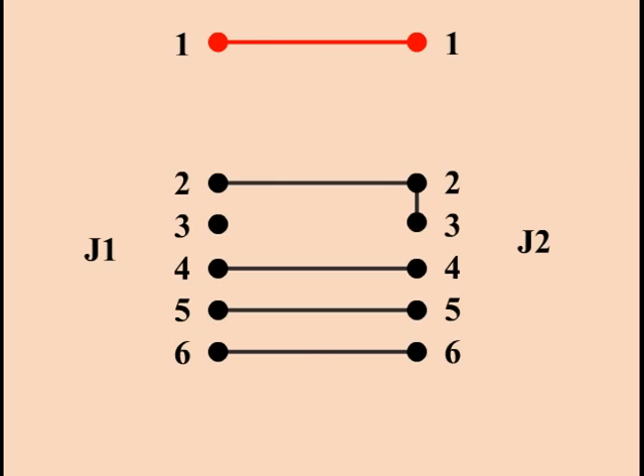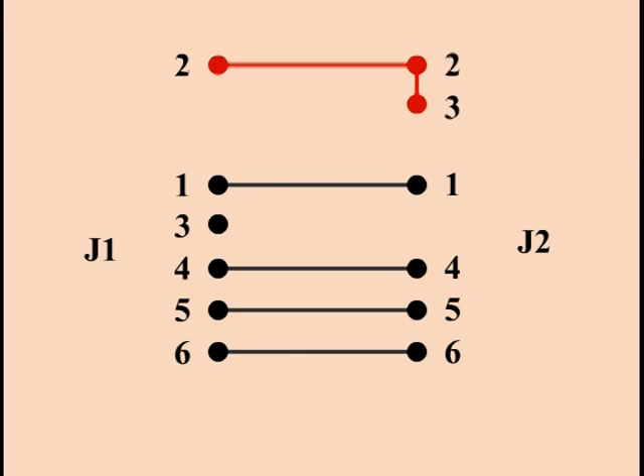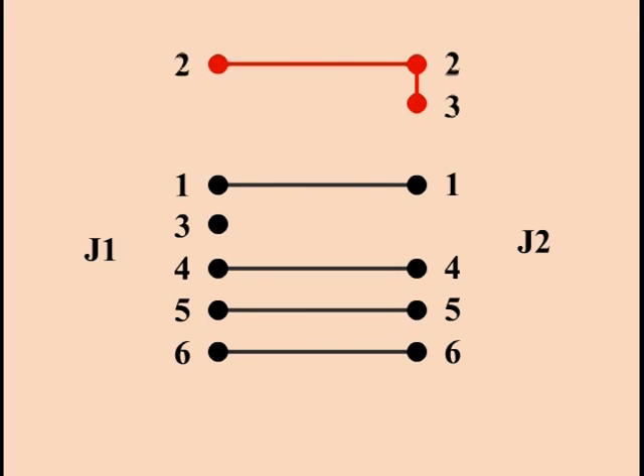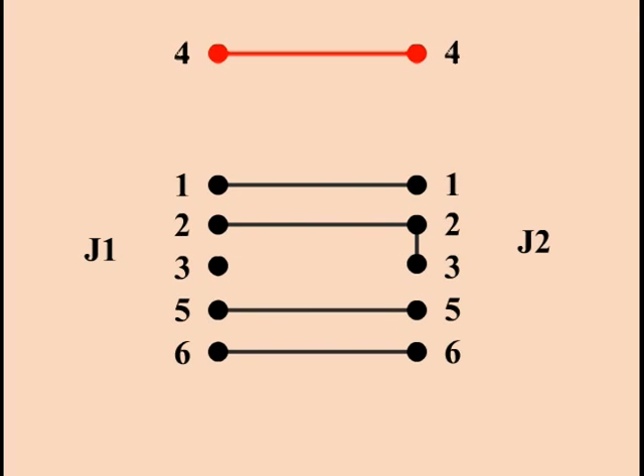The energy in net 1 is then discharged and net 2 is charged up while all other nets, including net 1, are held low. The hipot test proceeds this way until all nets have been tested against all other nets.